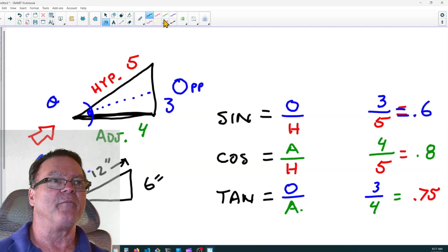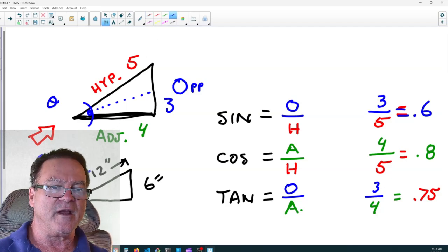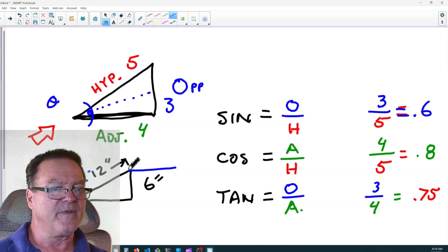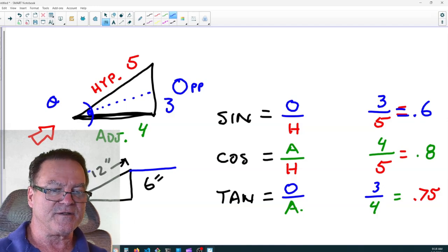We're talking about bending conduit. We're talking about how far apart to make our bends in order to make this 6-inch offset. So height of the obstruction times 2, and that'll give us our 12 inches. That'll give us the distance between those bends. All right, let's get back to it.